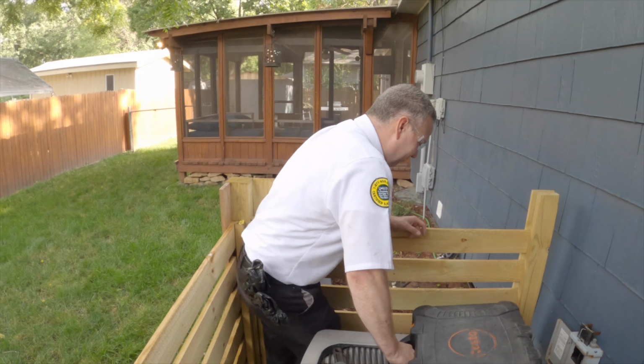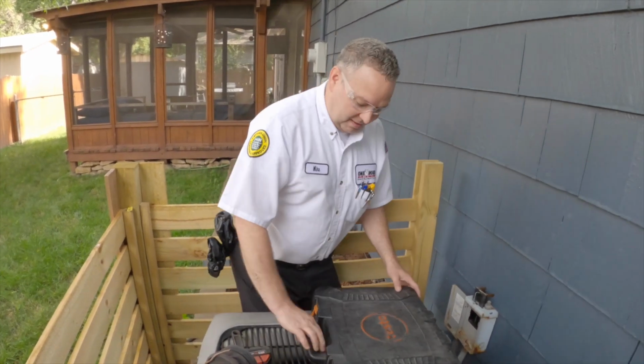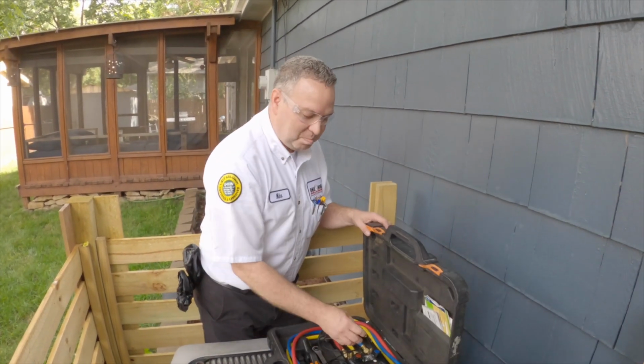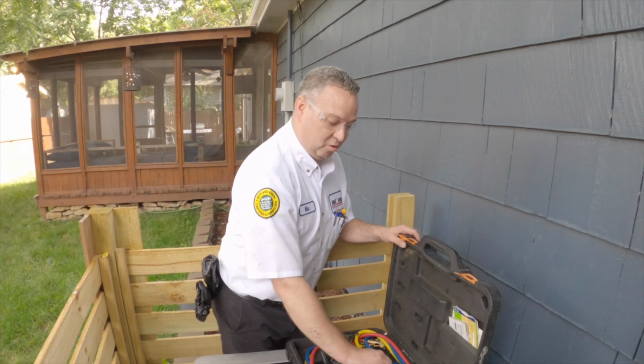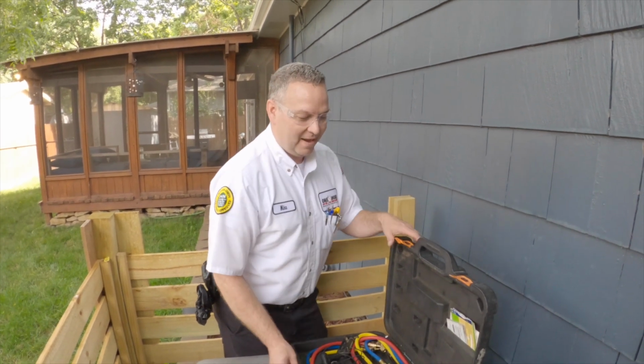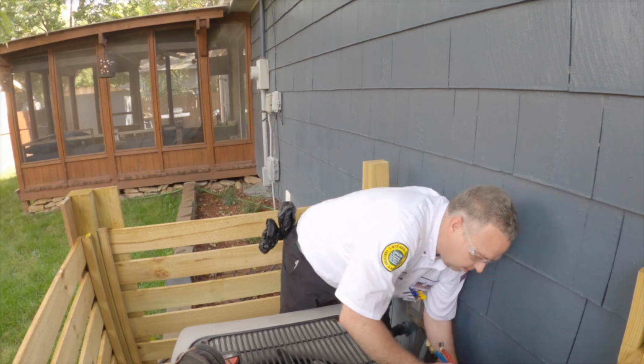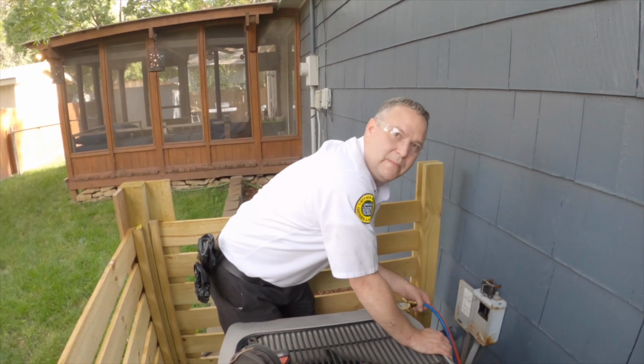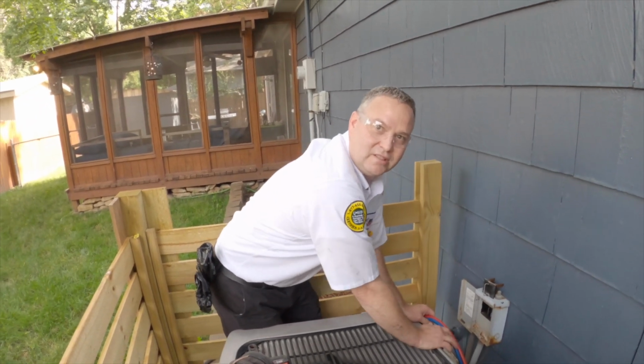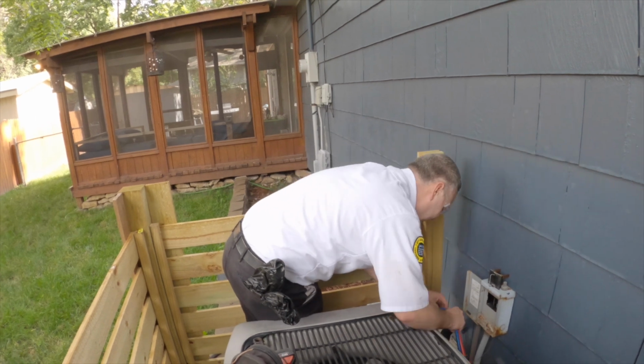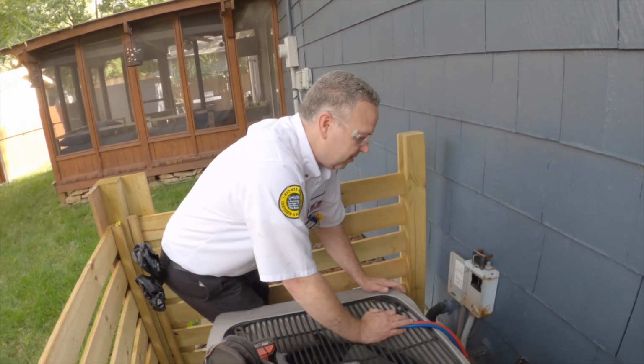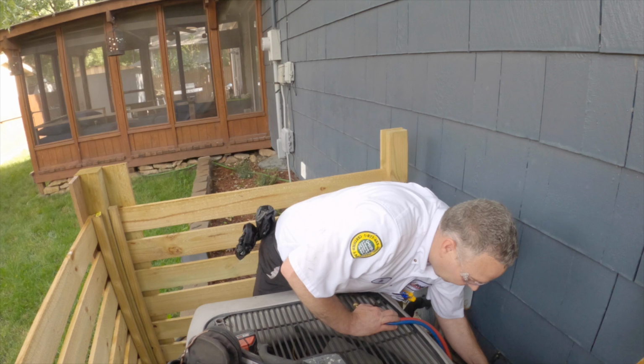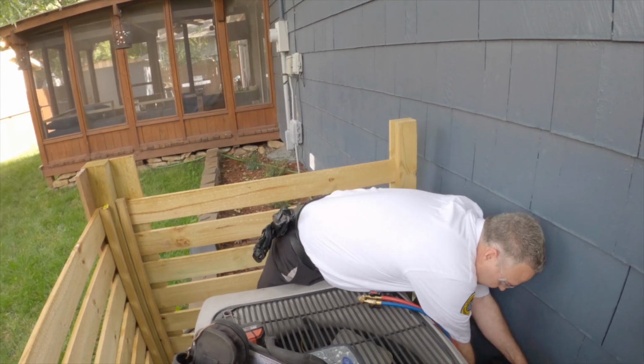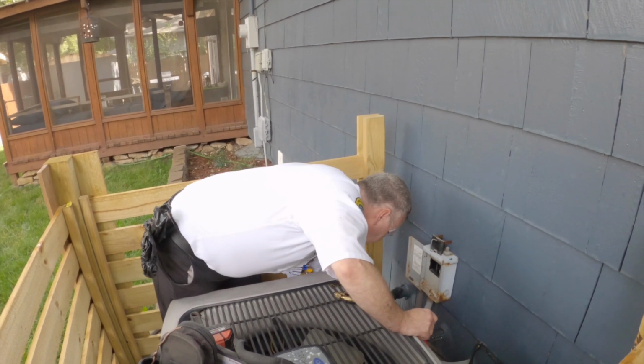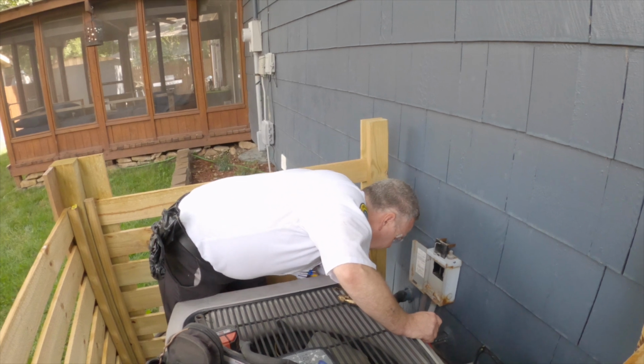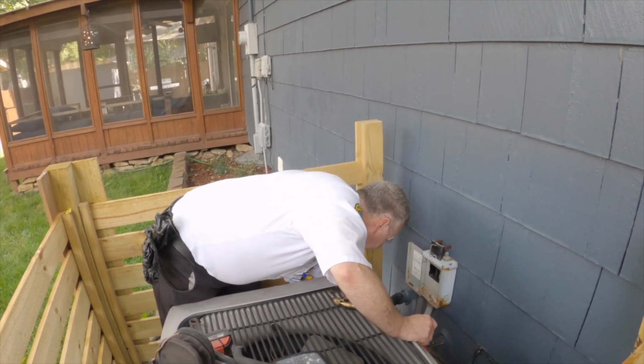So to you, it looked like, wow, you're just out of refrigerant, you've lost it all. Well, and the problem was this was around the time people were stealing refrigerant, so I thought maybe someone had stolen it out of this unit. Nope — you just had to open up the king valve, put your gauges on, and open the line to release that pressure to see what your refrigerant levels are.